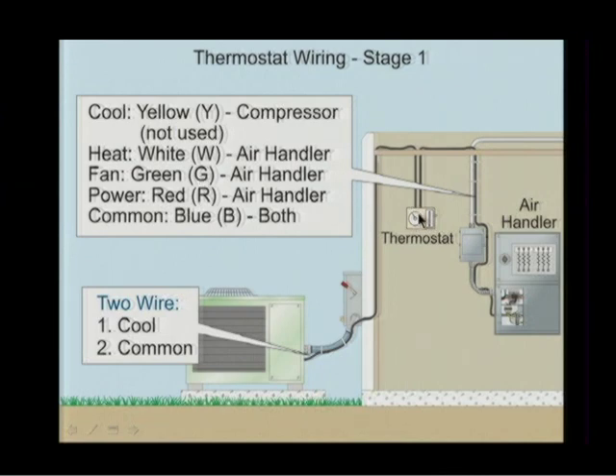So I'm going to take a green wire from the thermostat to the fan relay. I'm taking a yellow wire from the thermostat to the compressor relay. Then I have the heater, and heat is the white terminal or the white wire. Then from the thermostat, I'm going to take a white wire to the heating relay, and the heating relay has a blue wire going over to the common of the transformer.